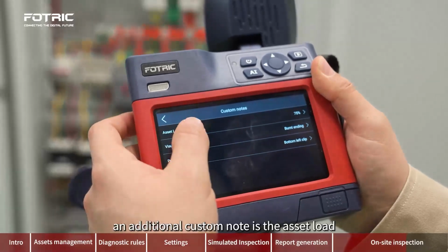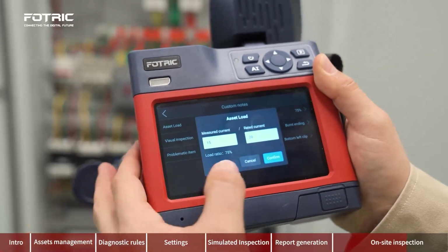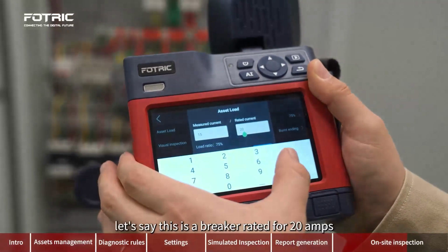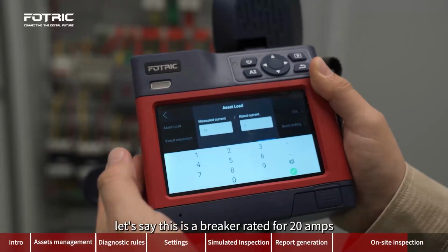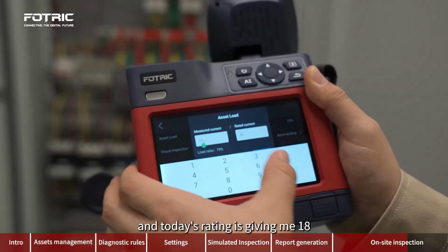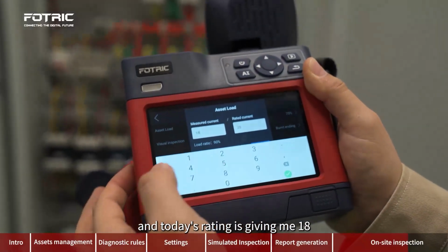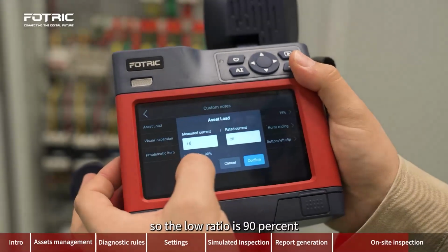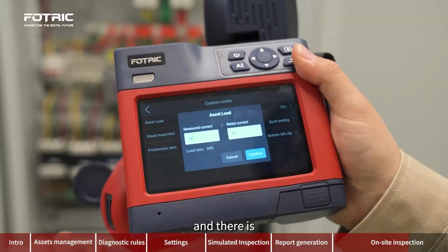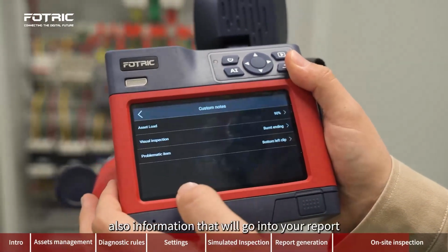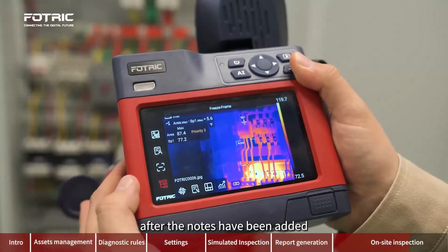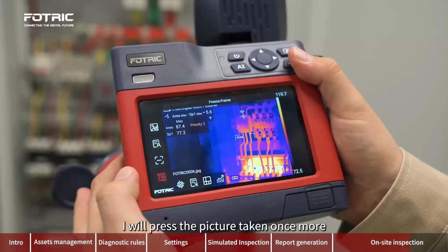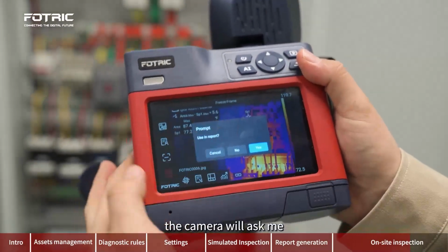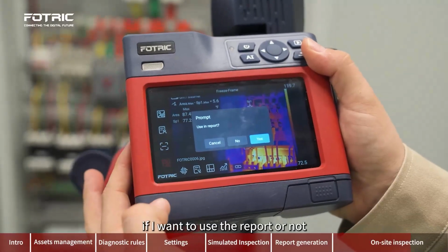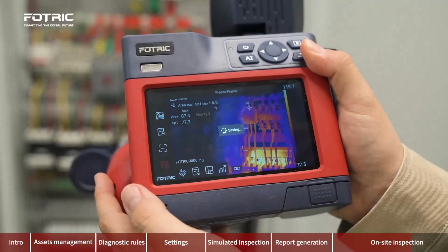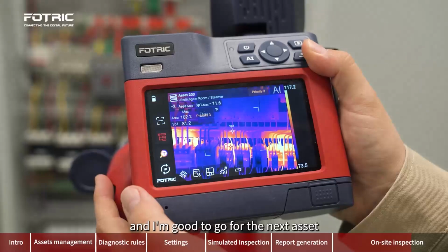An additional custom note is the asset load. You can input the rated current. Let's say this is a breaker rated for 20 amps and today's reading is giving me 18. So the load ratio is 90%, and that is also information that will go into the report. After the notes have been added, I will press the picture taken once more. The camera will ask me if I want to use it in the report or not. I'll say yes, and I'm good to go for the next asset.